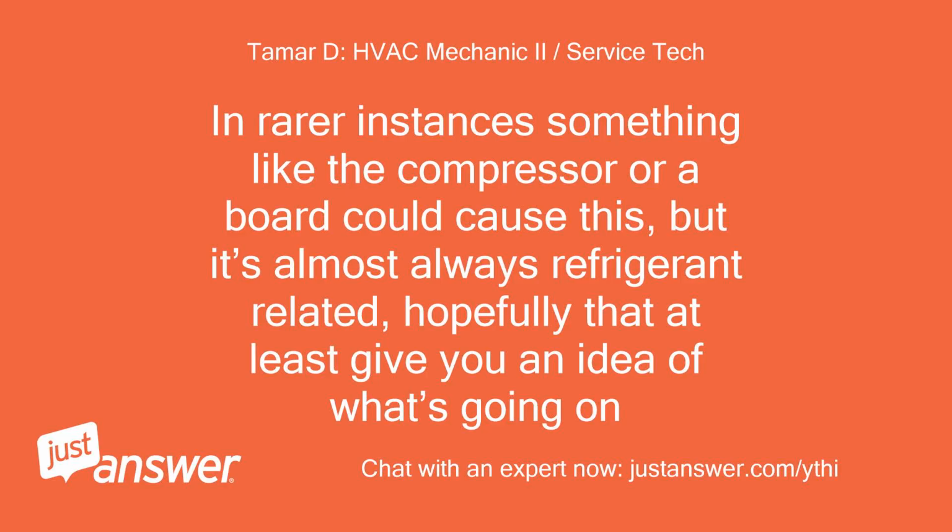In rarer instances, something like the compressor or a board could cause this, but it's almost always refrigerant related. Hopefully that at least gives you an idea of what's going on.